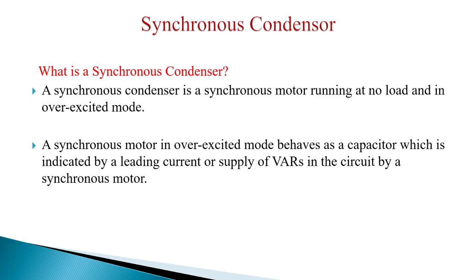A synchronous condenser is a synchronous motor running at no load and in overexcited mode. So a synchronous motor in overexcited mode will behave as a capacitor, which will be indicated by a leading current or supply of volt ampere reactives. What is VAR here? VAR is nothing but volt ampere reactive in the circuit supplied by a synchronous motor.